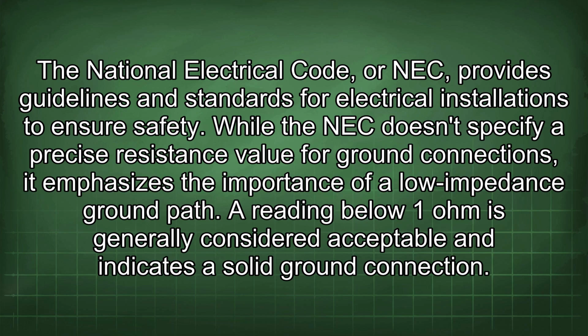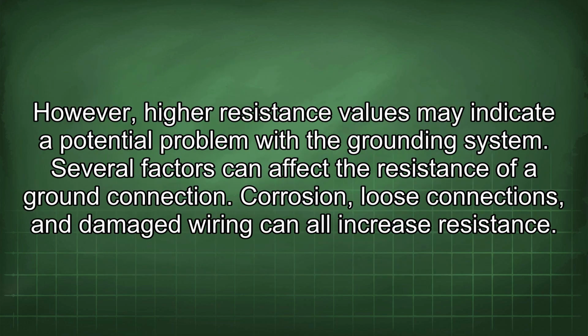The National Electrical Code, or NEC, provides guidelines and standards for electrical installations to ensure safety. While the NEC doesn't specify a precise resistance value for ground connections, it emphasizes the importance of a low impedance ground path. A reading below 1 ohm is generally considered acceptable and indicates a solid ground connection. However, higher resistance values may indicate a potential problem with the grounding system.